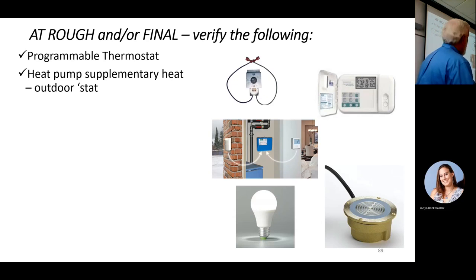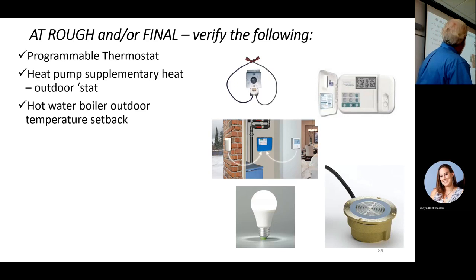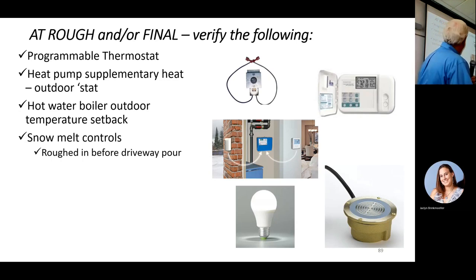Those either in HVAC, you know what I mean by this, heat pumps. If they're using electric supplementary heat or a heat strip that kicks on when you crank the thermostat up, you need an outdoor stat that keeps the strips off if it's warm enough outside to heat your space. Hot water boilers need a reset control that changes the temperature of your boiler water as the temperature varies outside.